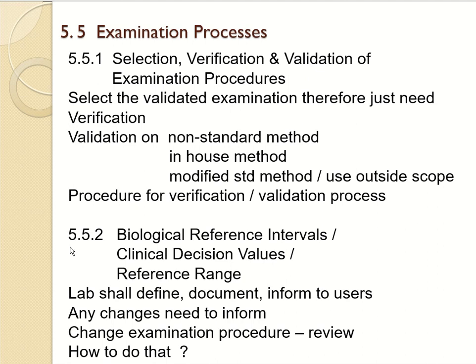Under clause 5.5.2, it states the biological reference intervals, or the short name, reference range. Yeah, the reference range of the test. So the lab shall define, document and inform users about the reference range of the tests that it offers. So any changes to the reference range need to be informed to the users or clients, and if there is any change in the examination procedure that could lead to a change in the result production, the lab needs to review the reference range.